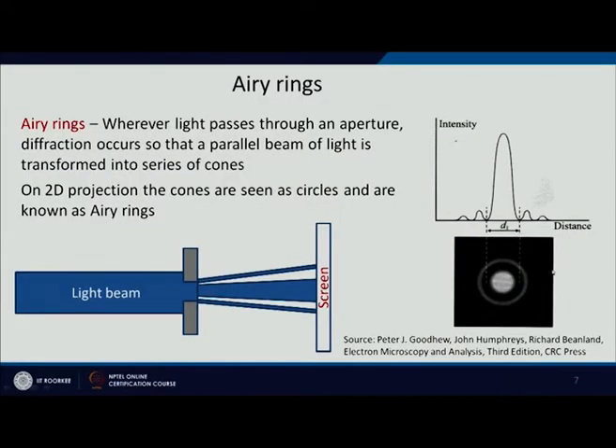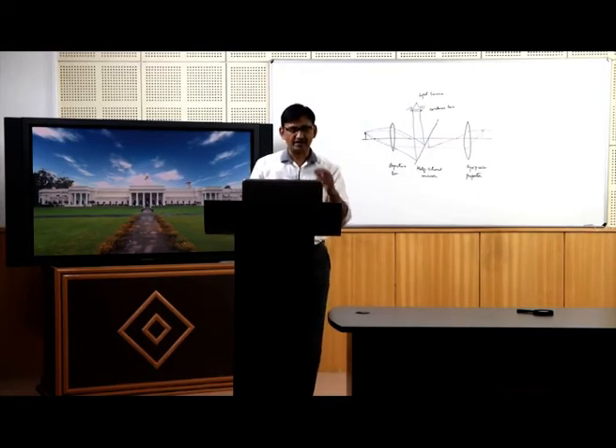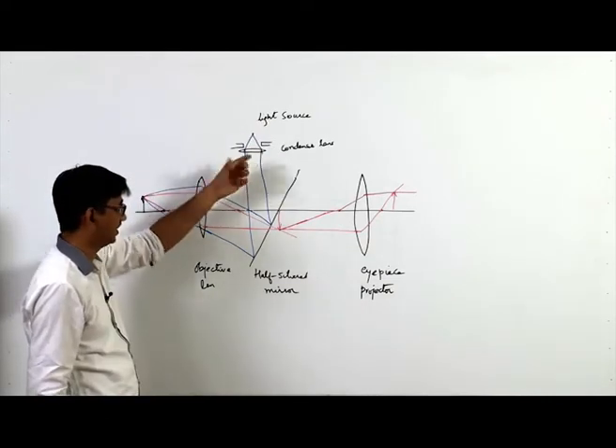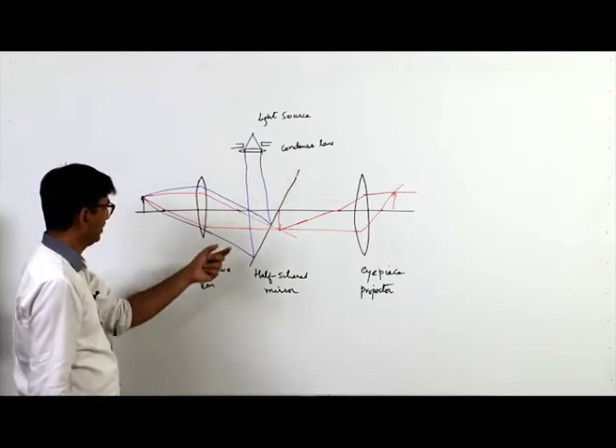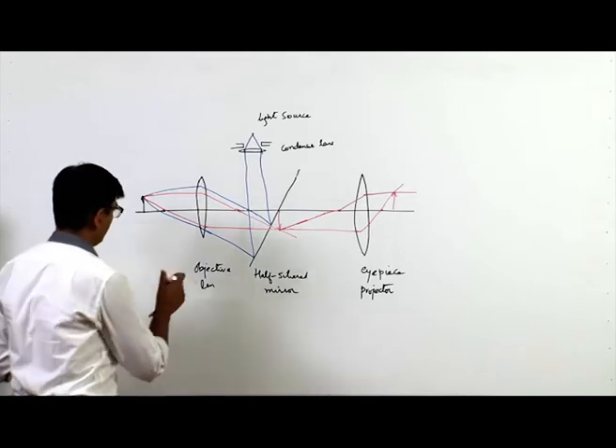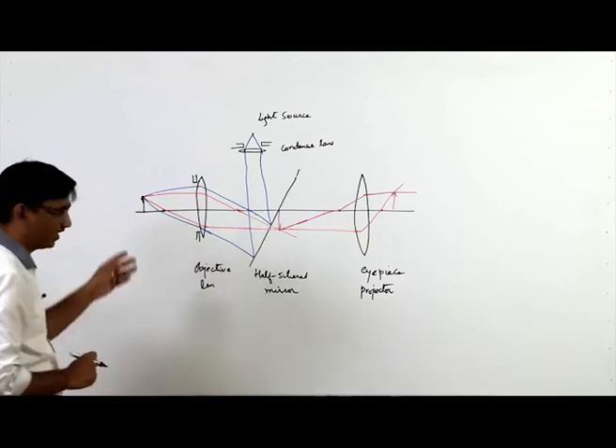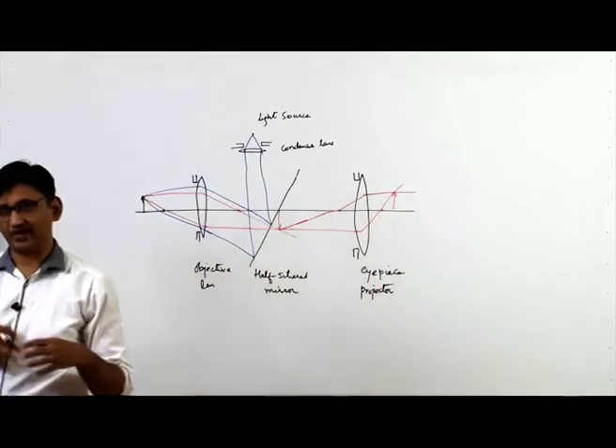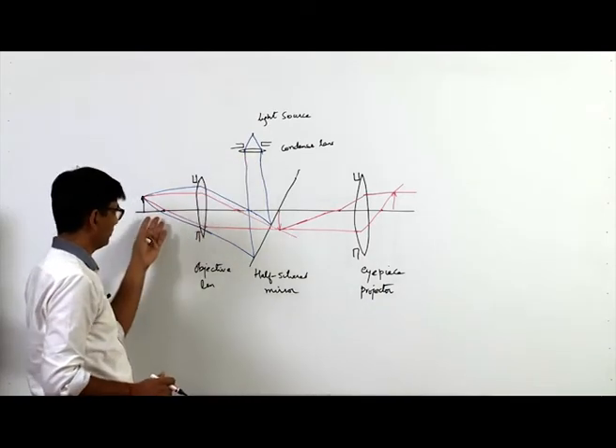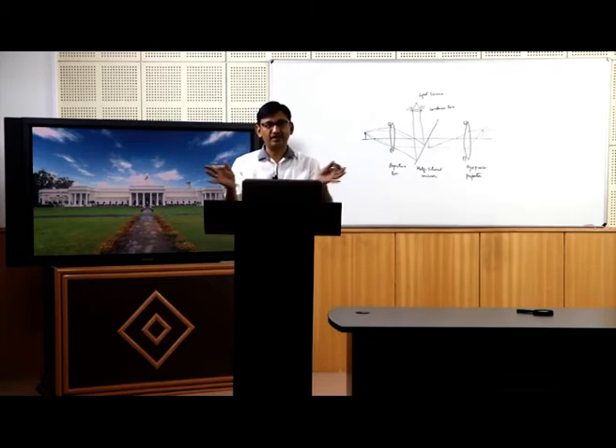So a parallel beam of light going through any opening forms this Airy ring pattern. In the microscope system there is a first aperture at the condenser lens, then after reflection the beam goes through the objective lens aperture, and then through another aperture at the eyepiece. So this light source undergoes Airy ring formation at three places, with the beam dividing into multiple beams at each, which is what reduces the resolution.